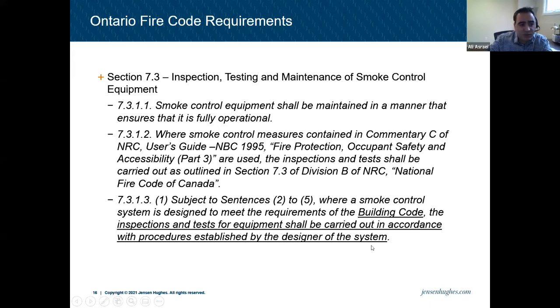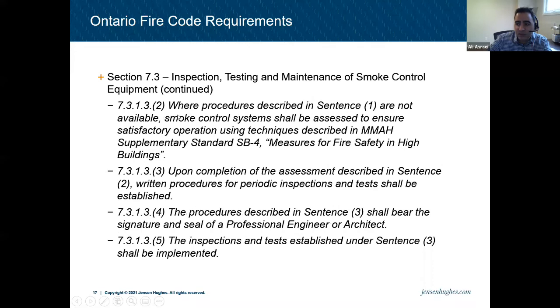So assuming we're talking about the existing building, we don't have this established procedure by the designer. When they're not available, the smoke control system shall be assessed to ensure satisfactory operation using techniques. And then the next sentence says that when you did that assessment, you have to put together a procedure. And then the next sentence says that whole procedure needs to be stamped by an engineer. So technically, if you're going backwards, you need an engineer to do all this work for you. And then after that, you can move forward with the maintenance procedure, right? So to me, that's the first step, to involve an engineer to see what's going on.